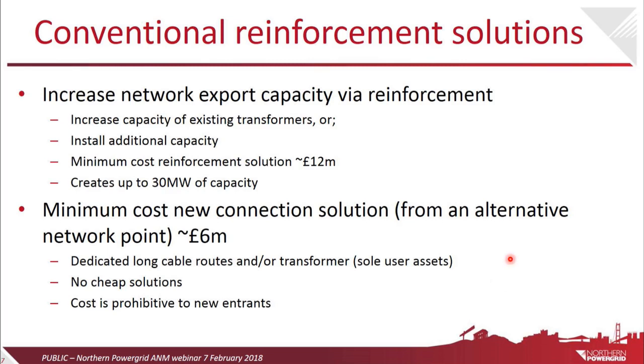So what do the conventional reinforcement solutions look like, and how much would they cost to get additional generation connected? So traditional reinforcement would require the replacement of the 132 to 66 kV grid transformers supplying the Driffield network with higher capacity units. These would cost in the region of around £12 million and would release about 30 megawatts of generation export capability. To get generation connected in the Driffield geographical area would require dedicated long cable routes out of the area to alternative connection points, i.e. outside the Driffield network.